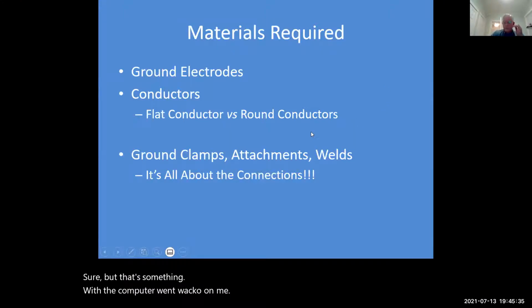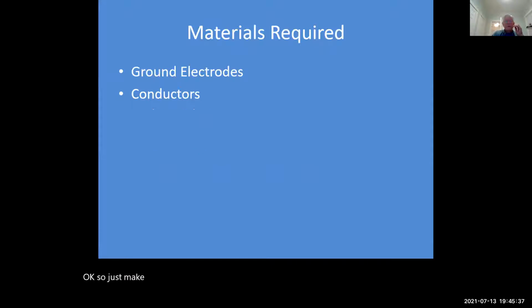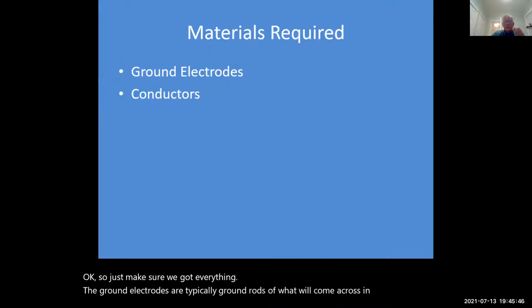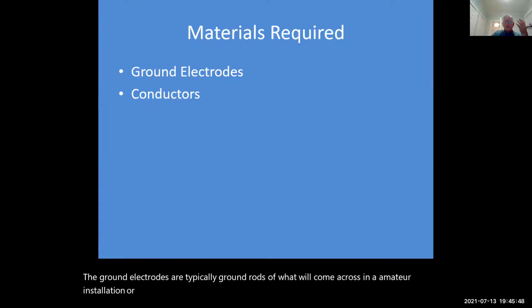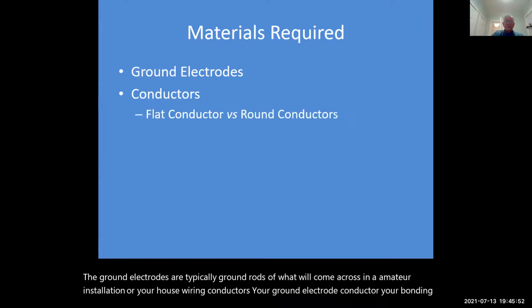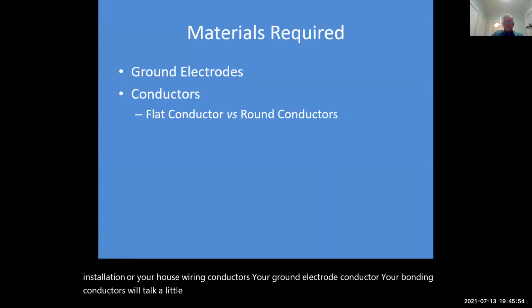Okay, so just make sure I got everything. The ground electrodes are typically ground rods, what we'll come across in an amateur installation or your house wiring. Conductors, your ground electrode conductor, your bonding conductors. We'll talk a little about the flat conductor versus round conductors.